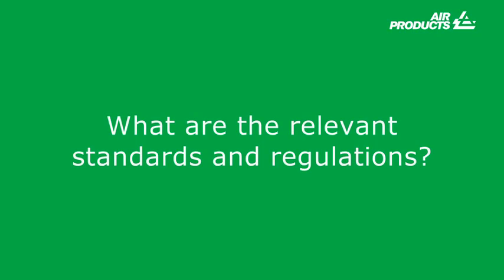What are the relevant standards and regulations? In the United Kingdom, we have the Health and Safety at Work Act and other standards issued by the IEC, the International Electrotechnical Commission. Back in 2009, a performance standard and associated guidance document was published by the IEC, relating to the performance requirements of detectors for flammable gases. It became a harmonised standard under the ATEX directive on the 1st of November 2010.